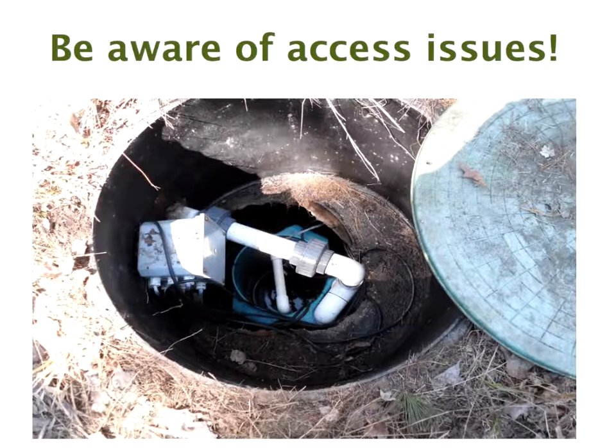Okay, access issues. If you have something like this, you can't get in there. Look at it. Everything's just too small to be able to get in. So make sure that, again, this is a design issue. This is dirt that's built up across the inside here, but it's also a design issue right from the beginning.